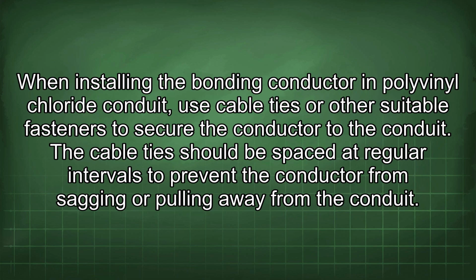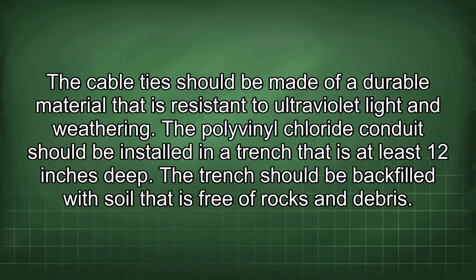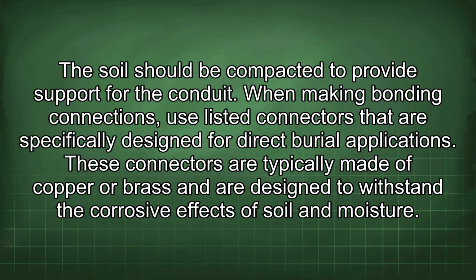When installing the bonding conductor in polyvinyl chloride conduit, use cable ties or other suitable fasteners to secure the conductor to the conduit. The cable ties should be spaced at regular intervals to prevent the conductor from sagging or pulling away from the conduit. The cable ties should be made of a durable material that is resistant to ultraviolet light and weathering. The polyvinyl chloride conduit should be installed in a trench that is at least 12 inches deep. The trench should be backfilled with soil that is free of rocks and debris. The soil should be compacted to provide support for the conduit.